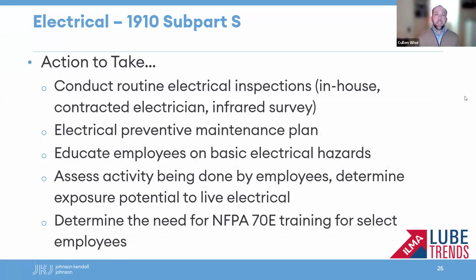All right. So, actions to take for electrical safety. Conduct routine electrical inspections. We suggest in-house you have an inspection protocol, primarily visual inspection, making sure everything is undamaged, it's secured, it's in good shape, it's not deteriorated. Consider contracting inspections to electricians. So probably a good part of a preventive maintenance plan is an annual electrical inspection. And we also suggest infrared surveys on some frequency, infrared surveys of your electrical equipment, mechanical equipment, breaker panels. Typically, this is done by a qualified electrician.